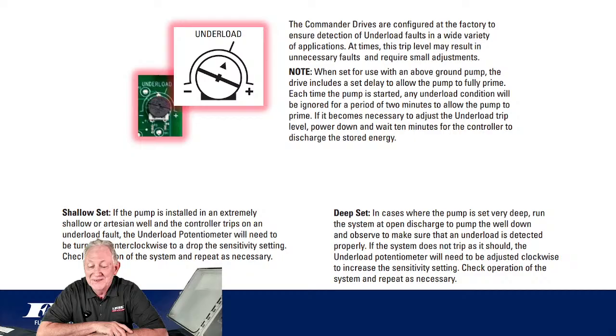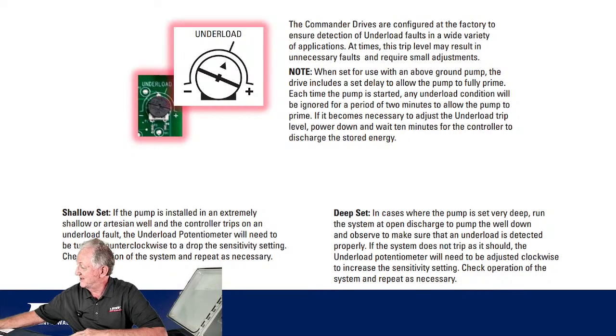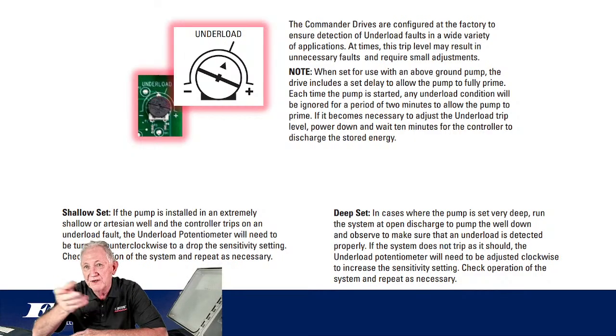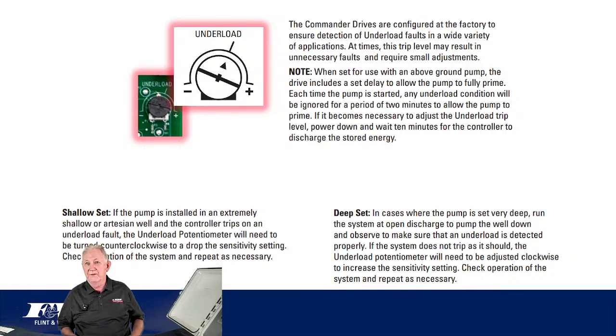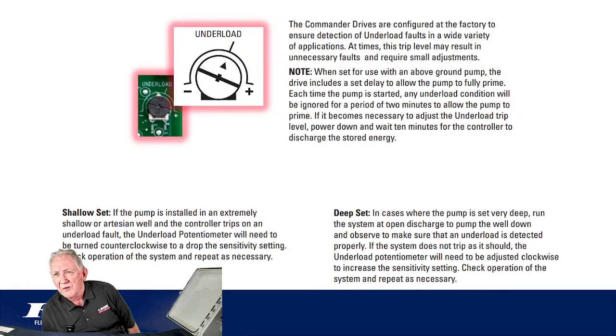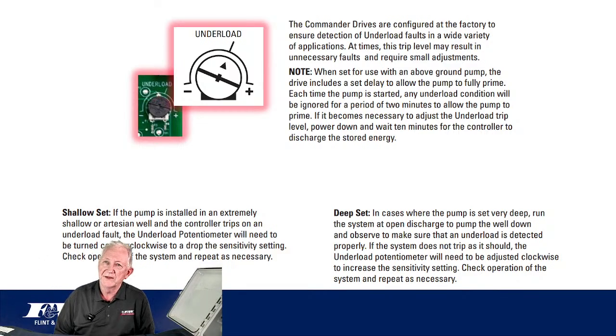Well, I guess it tells me we're getting close to the end of this broadcast. The last one is deep set. In cases where we have deep set pumps, and boy, Flint & Walling does a fantastic job with those deep set pumps, you run the system at open discharge to pump the well down properly. If the system does not trip as it should, the underload potentiometer will need to be adjusted clockwise to increase that sensitivity, and then check the operation again as necessary.